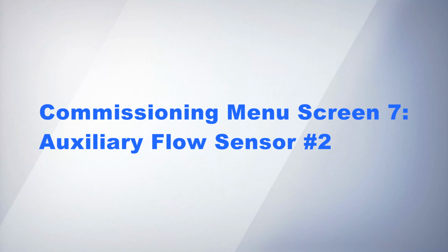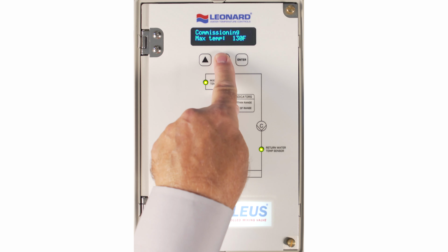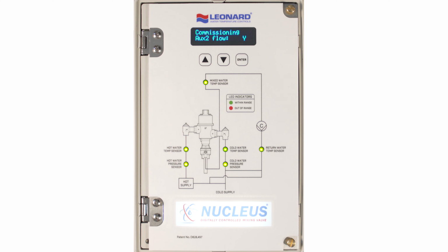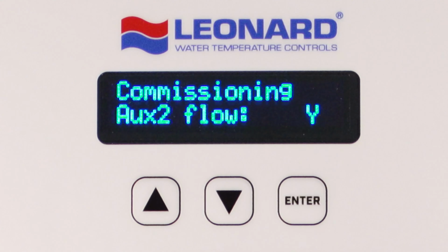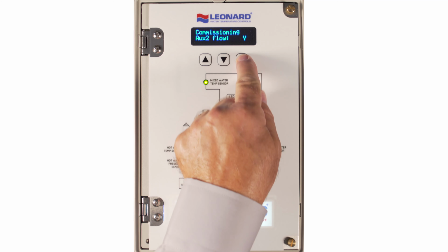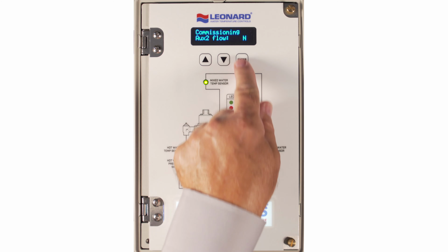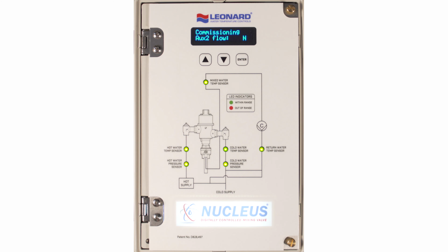Commissioning menu screen 7. Auxiliary flow sensor number 2. Pressing down 6 times displays AUX2 flow, no or yes. This indicates whether or not the configurable auxiliary channel, if utilized, is a second flow meter or a third pressure sensor supplied with the Nucleus unit. Select Y if a flow meter is used or N if a pressure sensor is used. See the Nucleus O&M manual for proper wiring configuration.